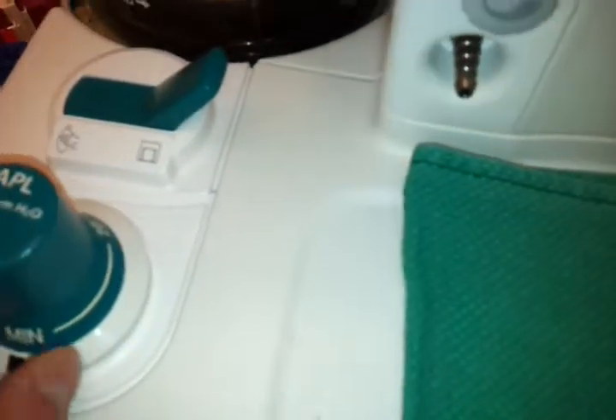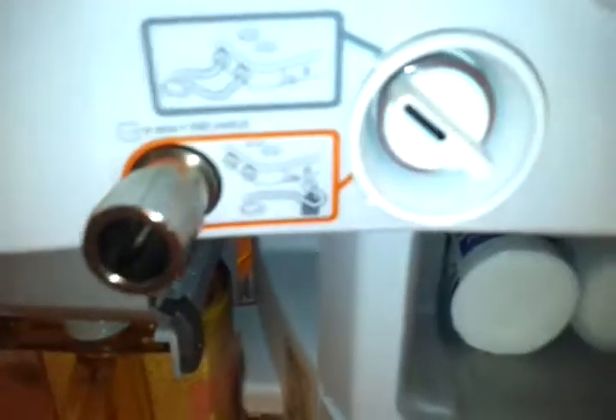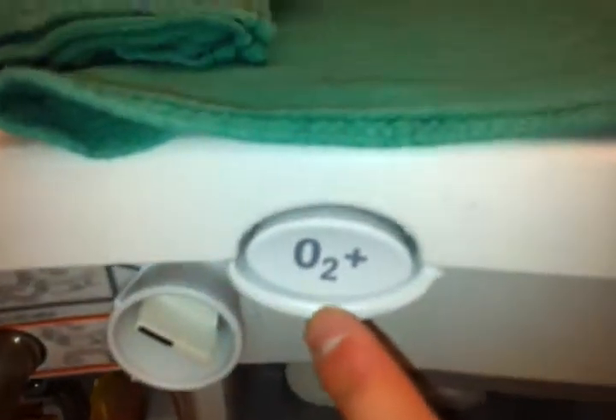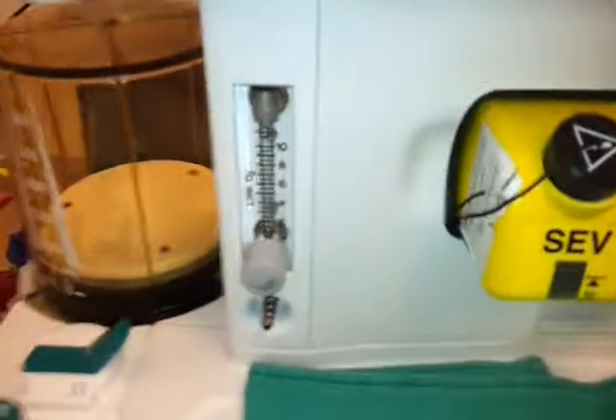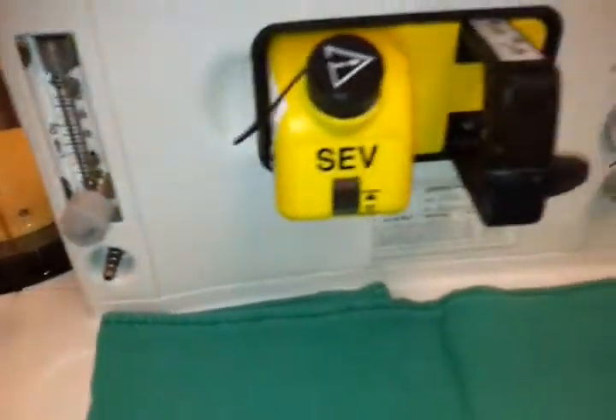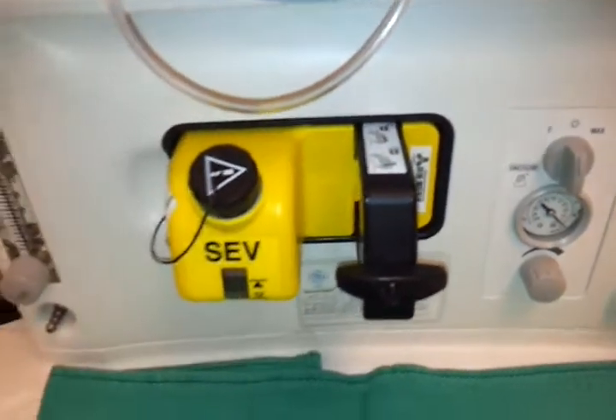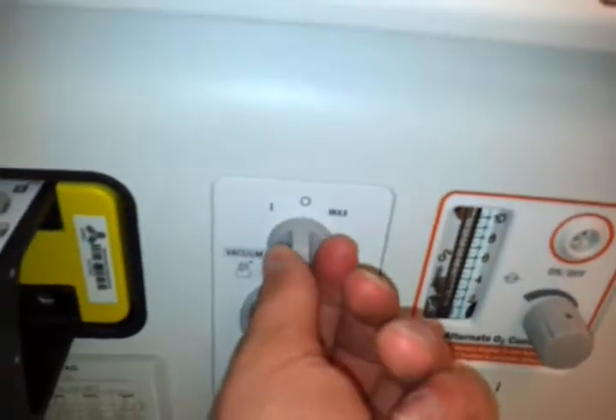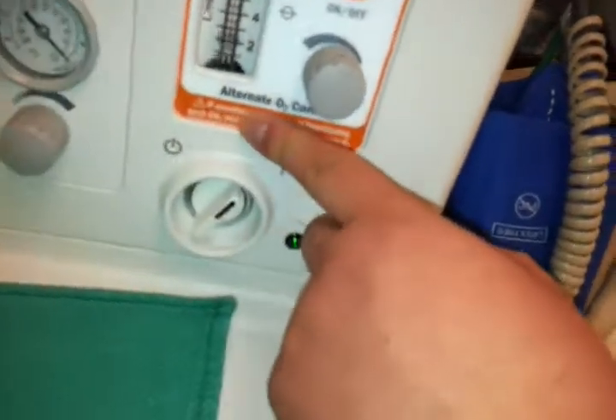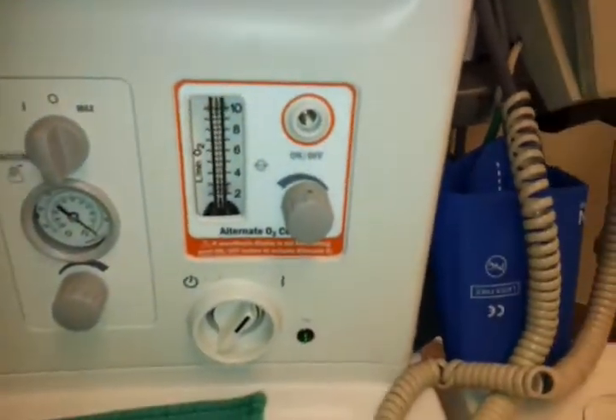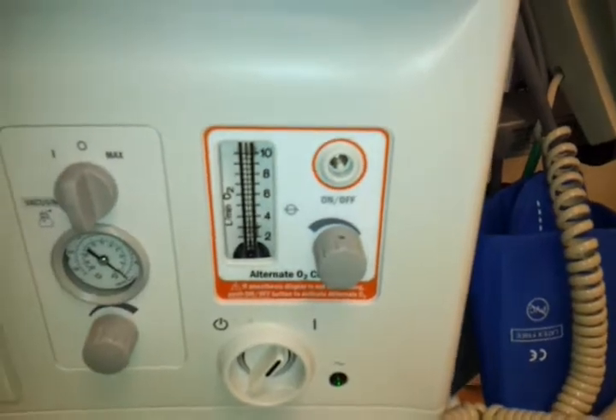Okay. So there's the bag and vent switch, which I already showed you. The APL valve is right here. For the most part it's set to min unless you're going to bag someone. There's the ACGO switch set to circle, O2 flush valve, which we're going to show you later. On the front there's an extra flow meter in case you need the bag, the volatile gas that's set up. Your suction supplies are right here, and your alternate O2 control is right there. You pretty much never use that unless the blender fails.